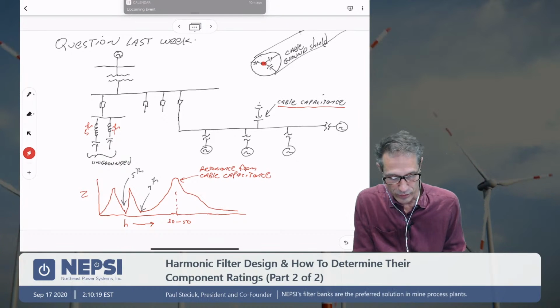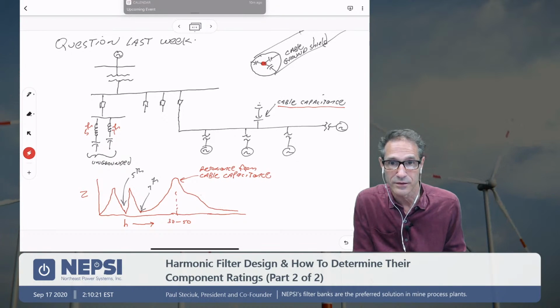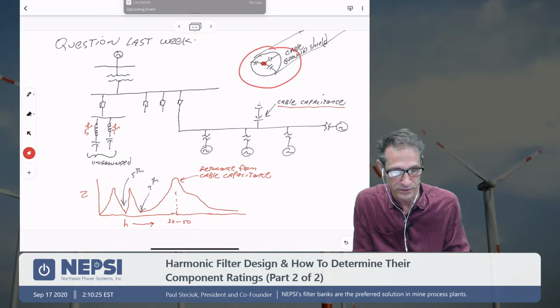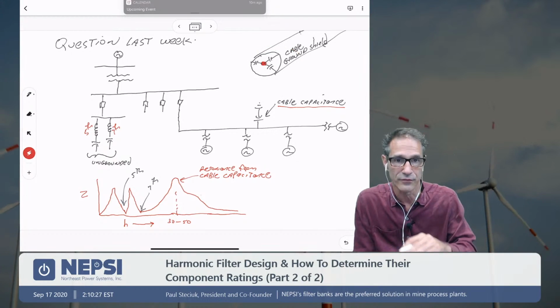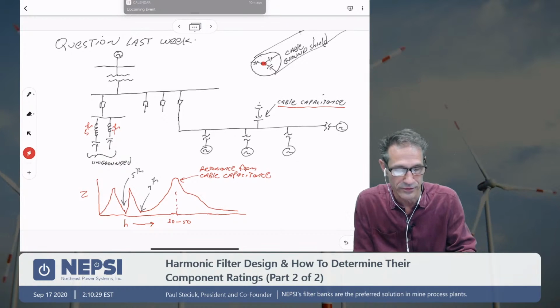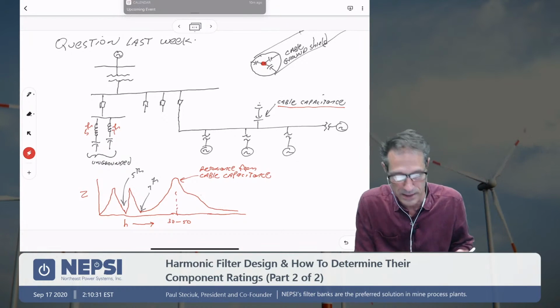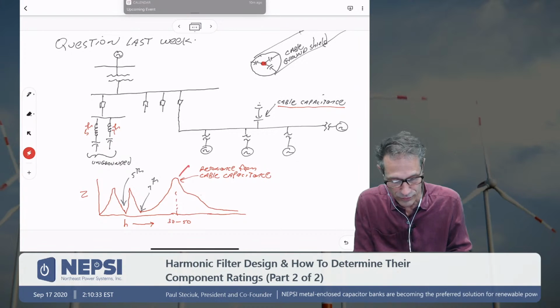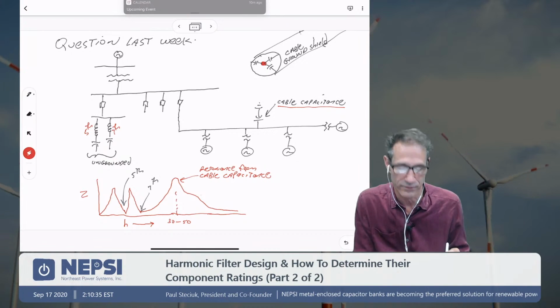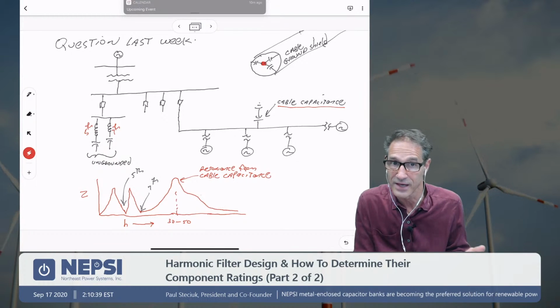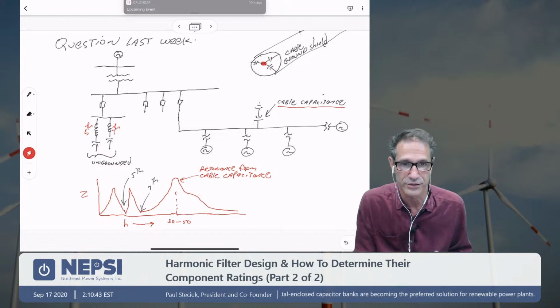And we will get another rise in the impedance scan, and that will be resonance caused by the cable capacitance here, which is really a combination of all that distributed capacitance within the cables, and sometimes it's many, many miles. That will cause a resonance, and really it's the balanced portion of that capacitive impedance, which if it's cables, it's going to be very balanced capacitance, and it will show itself in the positive sequence network.